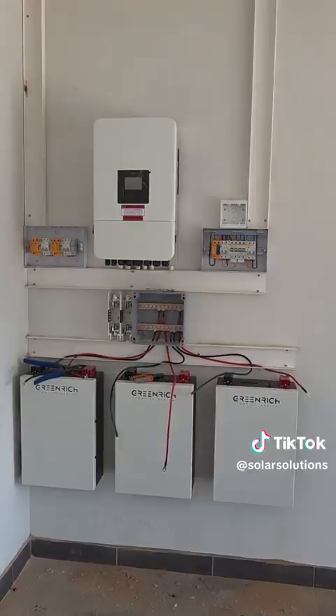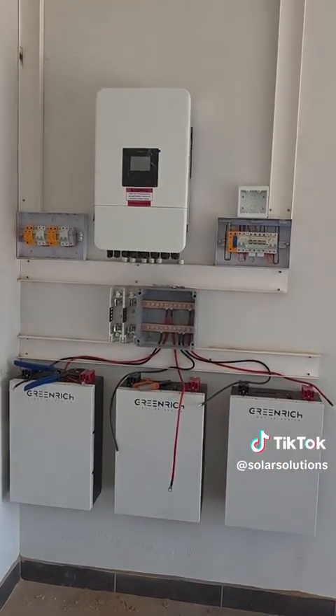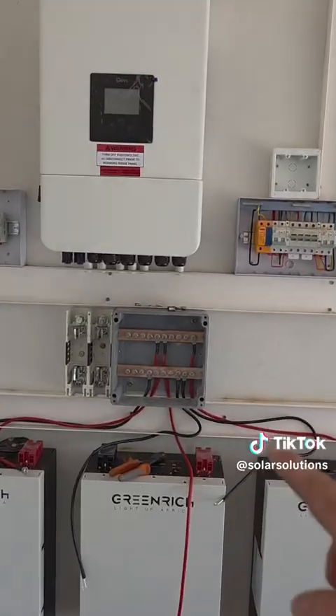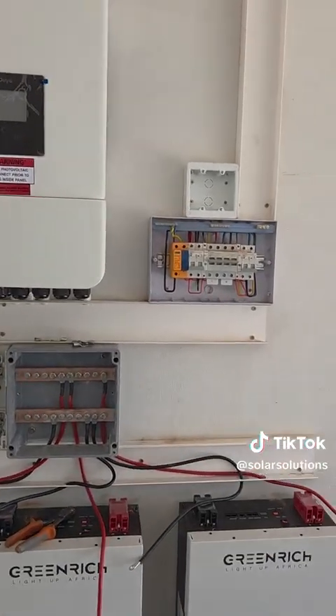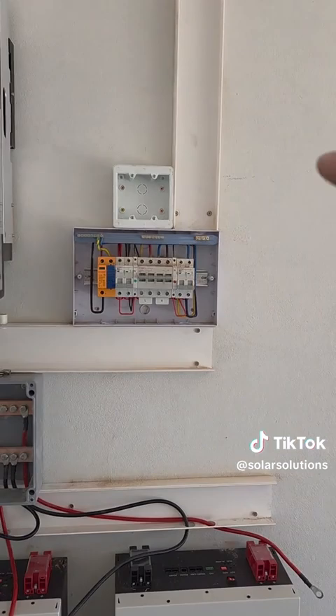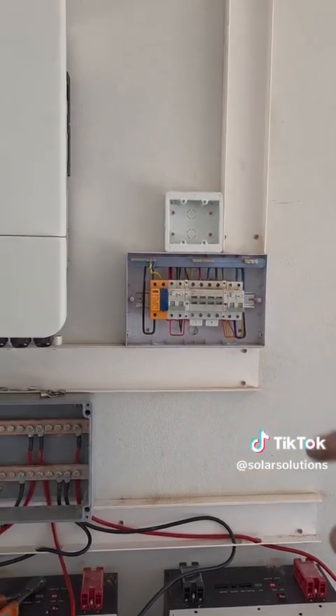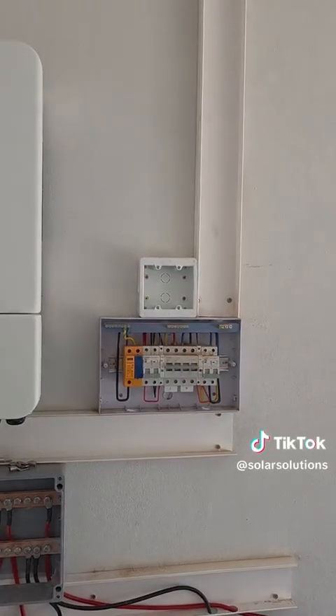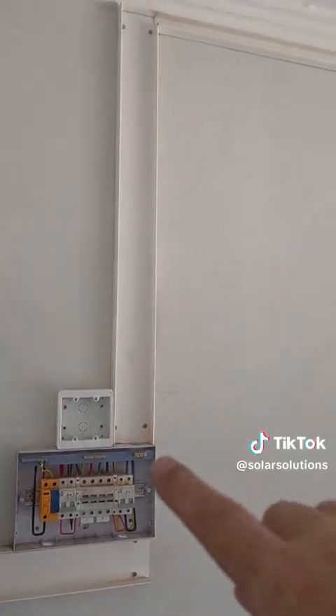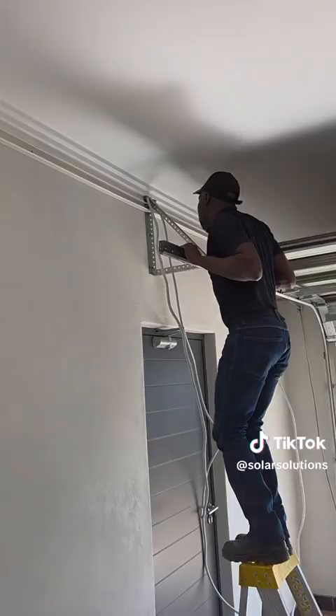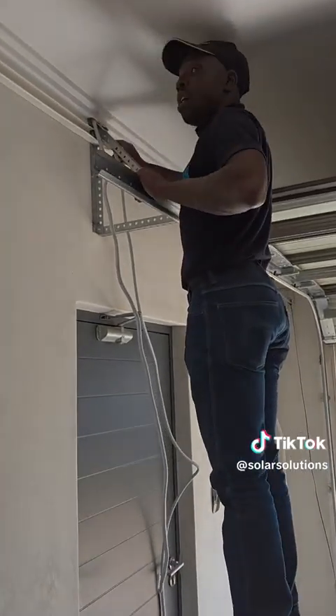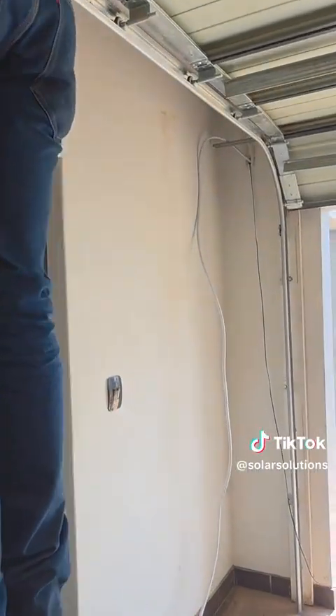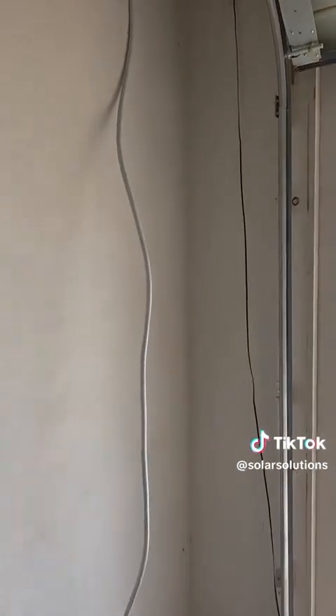Another quick update, guys - we're busy doing the battery cables from the bus bar to the various batteries, and then we'll go through to the inverter. Got the AC combiner pre-wired and mounted, the Eskom or prepaid plug mounted, a box mounted already as well, and trunking all installed. We're just busy pulling through the AC cable with the speaker cable, which is for the CT clamp.